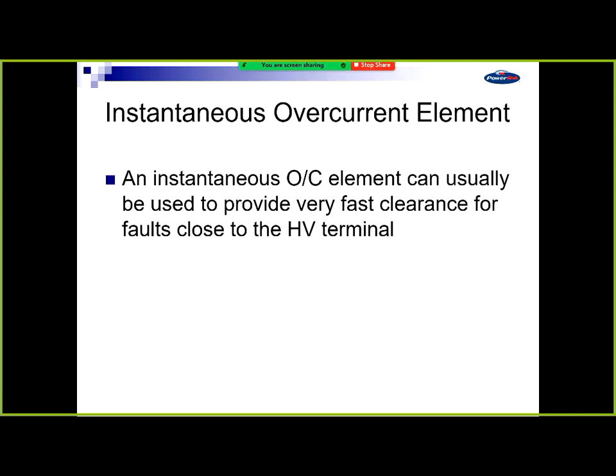Instantaneous overcurrents are actually quite good. They can detect faults on the HV side really well. What you've got in your transformer is a lump of impedance. The fault level on one side might be 10,000 amps for the HV side, the 132 kV side. A fault on the low voltage side might only be 2,000 amps on the HV side, because it's 5,000 or 6,000 on the low voltage side, but as seen from the HV side, it's only 2,000 amps.